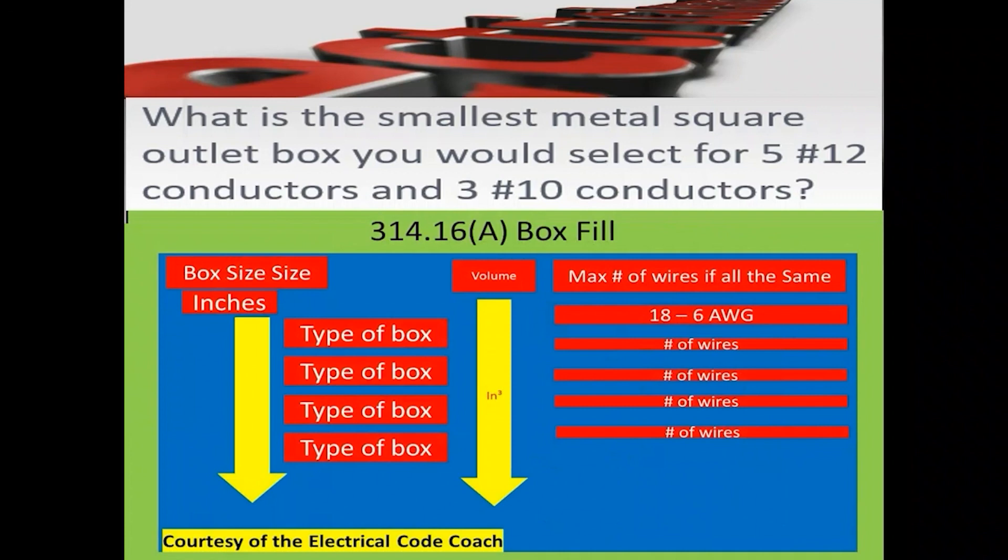So now we're going to head to table 314.16a and the first thing we're going to do is find our type of box. So our type of box is right here. Then we're going to come over to this middle column, the volume column, and we're going to go down and find a square box that just fits the conductors. And in this case, it's a four by one and a half. Great job.